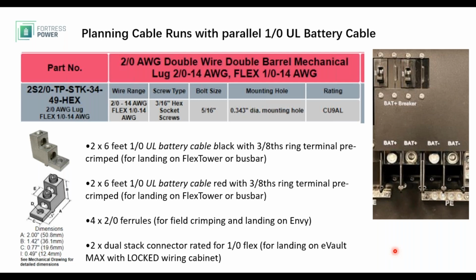So if you were to put it with one eVault Max, which has a discharge capability of 250 amps, we would have to bridge these ports, right? And one way to do it is if you have 2 cables going into this double wire, double barrel mechanical lug, and then connect that directly into the eVault Max's battery terminals. That's one way to do it.